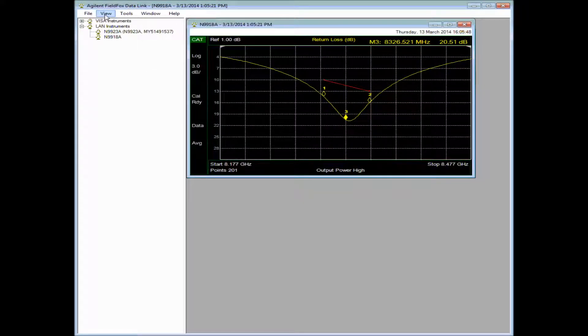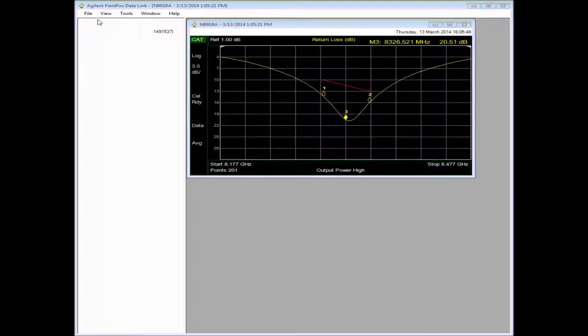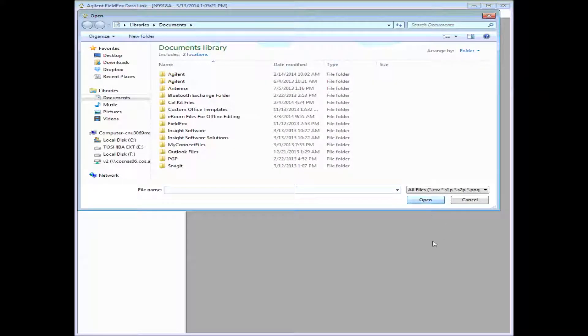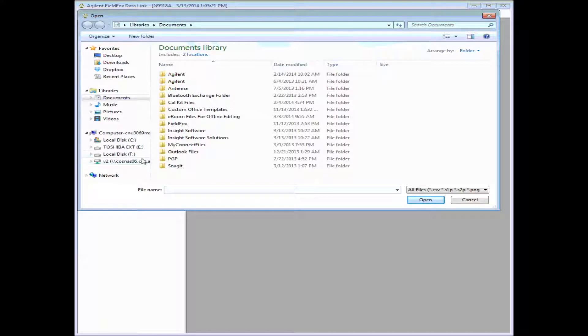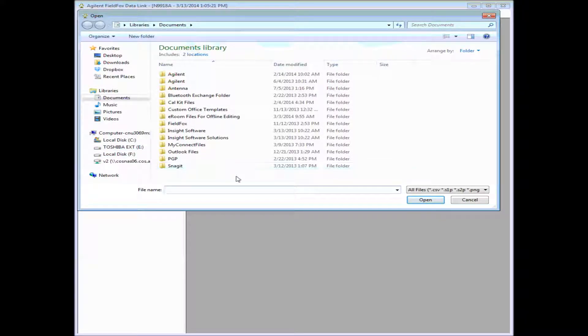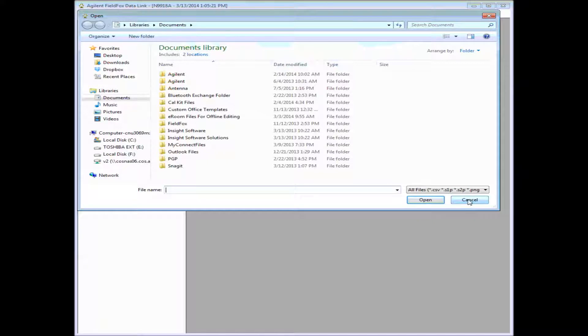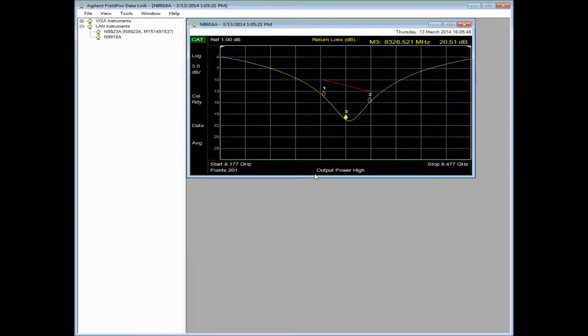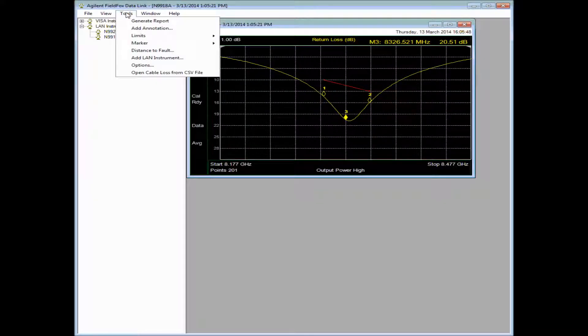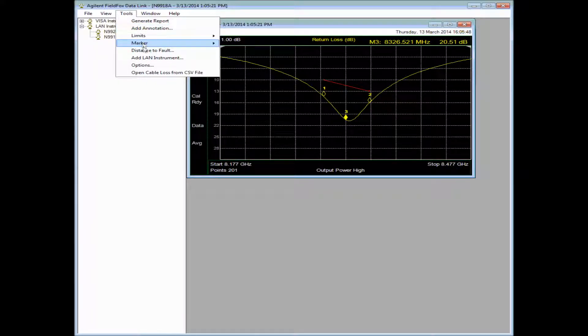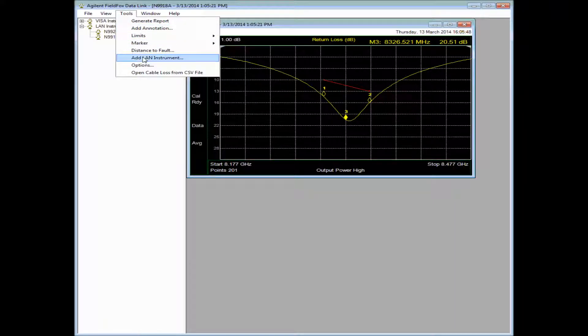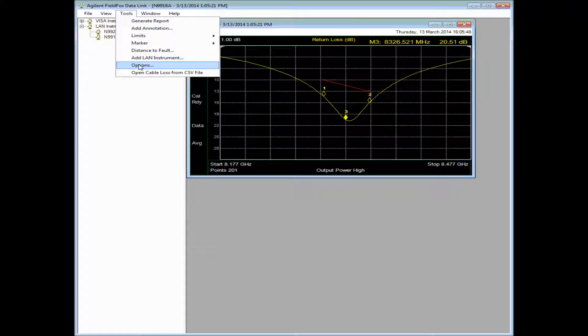We can also do some other things under File. Let's see if we can get into the menu of the FieldFox. Actually, we could open a CSV file or an S1P file, but that's not what we want to do at this point. We can generate reports, add annotations to this plot, add other instruments, etc.